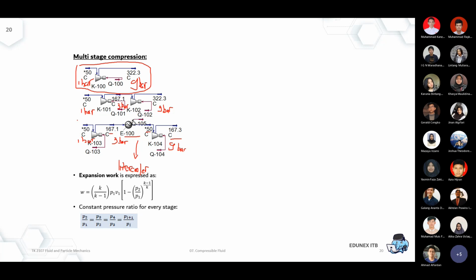I briefly state to you that a multi-stage compressor is commonly installed. The objective is to limit the temperature and to limit the duty. You can see the illustration over here, especially about the temperature. It can be seen very visibly that when you force the compression ratio to be 9 to 1, then you get a very hot temperature.